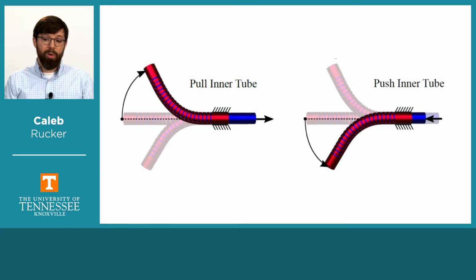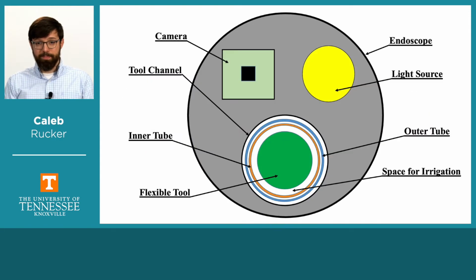We can then pull or push the inner tube in and out of the outer tube. This causes the device to bend because of the asymmetric stiffness that we designed into the tube cut patterns. By controlling the push-pull motion and the rotation of the tubes, either manually or robotically, we can then steer the device and reach many locations in space.